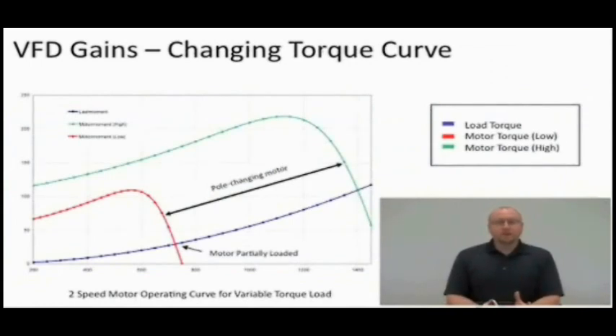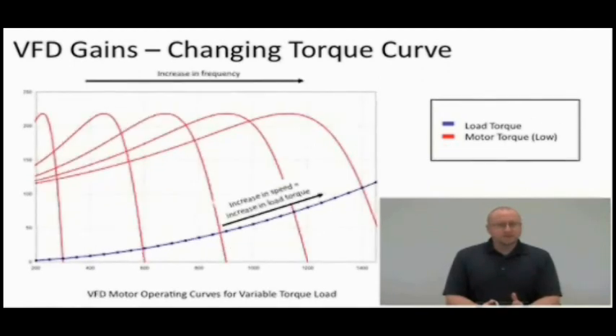Another thing that a variable frequency drive can do for you, take a look at this system. We have a variable torque load, which could be a pump or a fan, anything that changes the amount of load as speed changes. These torque versus speed curves are for a 2-speed motor. Actually, you're changing between the poles when you operate. This is a typical way to control the speed before frequency inverters came along. If we look at the same system being run by a frequency inverter, there's a different torque versus speed curve for each speed set point.